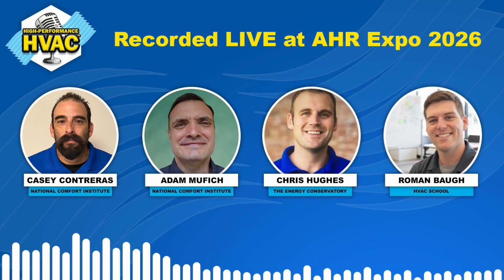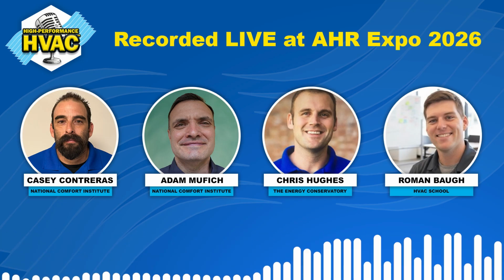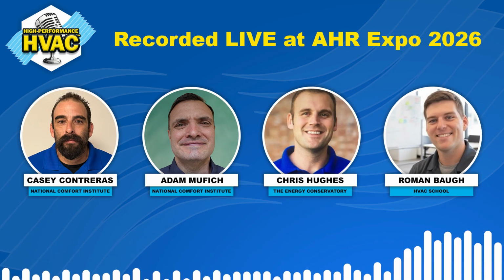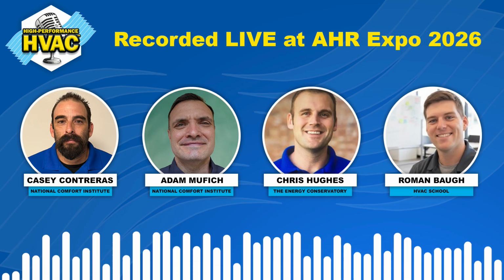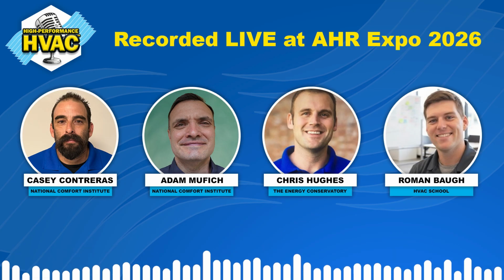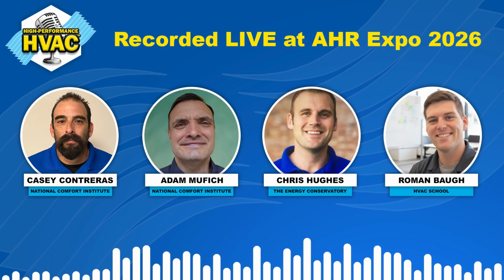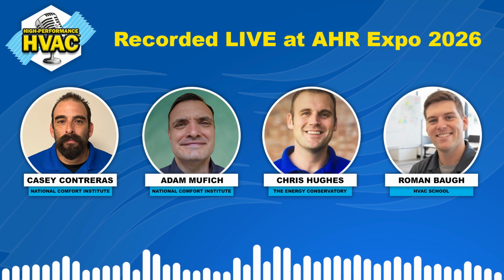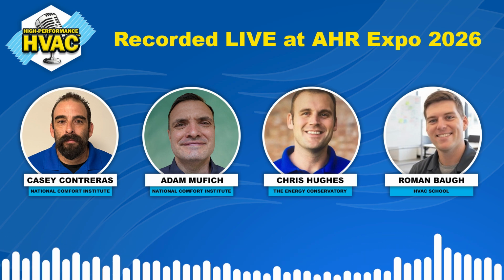So RPS on the undercharge situation in heating. Because I have 4 zones, I had 2 small zones calling. There were 9,000 BTU units, 18,000 BTUs calling for heat. RPS was like 45. Max speed is 105. So it's like middle of the road, 50%.